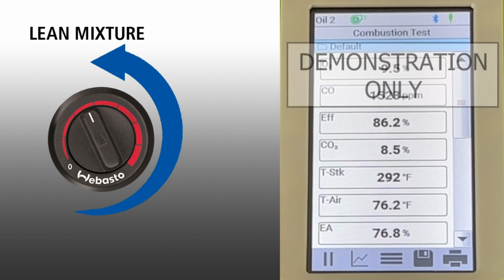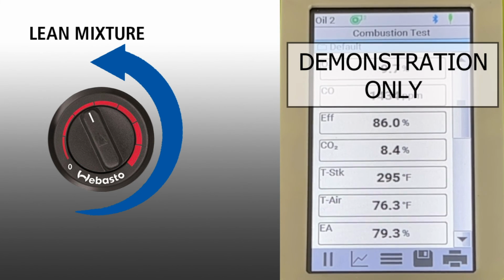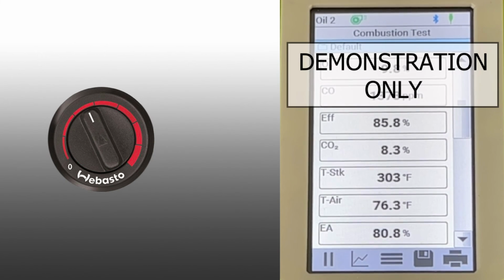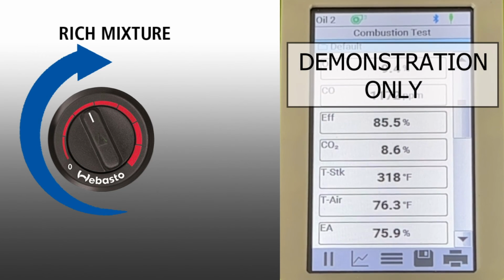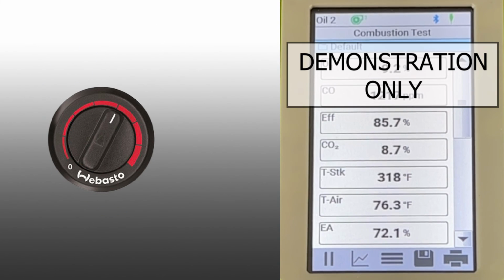Turn the heater on to the 12 o'clock position. A flashing indicator light lets you know that the heater is ready for adjustment. Turn the knob in small increments, waiting a few minutes between adjustments. Observe the CO2 reading. Make more small adjustments as needed. Make sure you allow a few moments for the heater to stabilize before making more adjustments. When the CO2 is in the desired range, simply disconnect the brown wire from ground. This saves the setting.